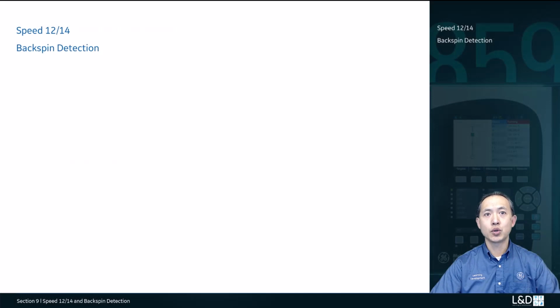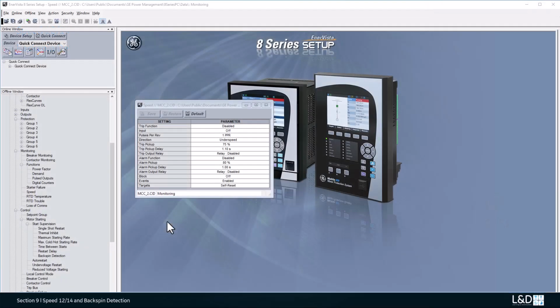In this session, we'll introduce the overspeed 12 and underspeed 14 elements and backspin detection. The contact input 4 is defaulted as a speed switch in 859, but any of the input contacts can be used to read the pulses from the input source. The source of the pulses can be an inductive proximity probe or a Hall effect gear tooth sensor. The speed algorithm calculates the number of pulses in the window length and converts it into an RPM value. A minimum pulse width of 10% of a resolution is required to detect a pulse from the pulse source. The element can be set to two modes, underspeed and overspeed, under the set points of the direction.